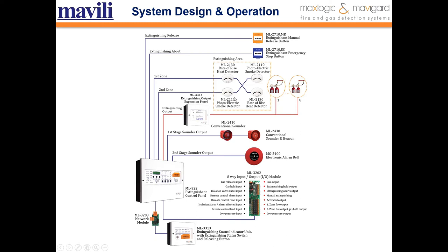Most panels work on the cross-zone principle because the extinguishing gases are expensive materials — we don't want to release them immediately; we need to be sure there is a real fire before releasing the gas. Also, if it is a false alarm and you don't want to start the extinguishing process, you can press the extinguishing emergency stop button. Or if an accident happened and detectors didn't detect the signal, you can press the extinguishing manual release button to start the extinguishing process immediately.